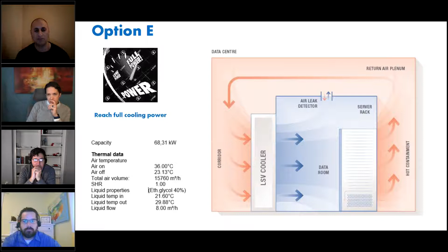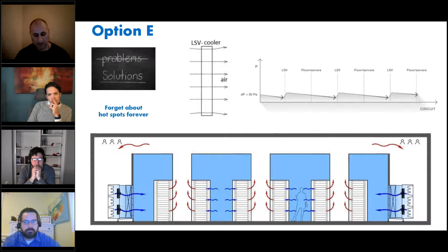The large cross-section of the coolers gives a low, uniform airflow rate along the entire path with a resistance of less than 30 Pascal, which creates conditions for the absence of pressure drops that could lead to the appearance of the Venturi effect and overheating zones. On the other hand, it is an opportunity to work without overpressure, to drastically reduce the power of fans and their heat dissipation. In all existing LSV data centers, service staff are not aware of problems with overheating zones.